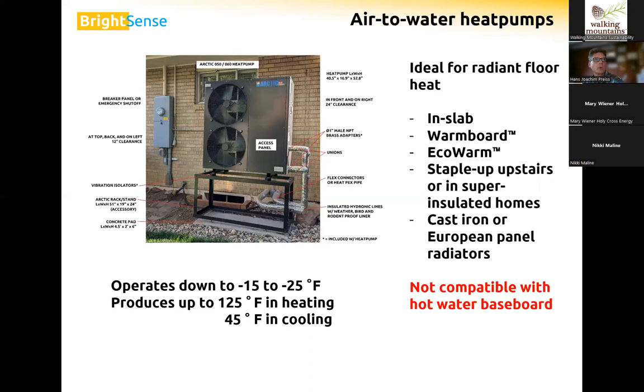Low temperature means we are able to operate down to negative 15 to negative 25 degrees. That depends a little on humidity, wind, sunshine. That all plays a role. That's why there's not a really hard cutoff. The heat pump will try to operate as low as possible. It's just that at one point, when it's really bitter cold, there's not much that the heat pump can absorb from this frigid outside air.